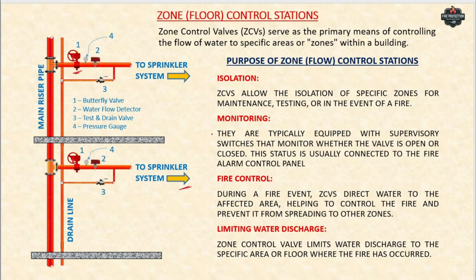And the second is monitoring and alarm integration. These valves are typically equipped with supervisory switches that are connected to the building fire alarm system. If a valve is closed or tampered with, an alarm will be triggered to notify building occupants to escape. Here we have some wires, and these wires are connected to the fire alarm panel. So if someone closes the valve, it will send a signal to the fire alarm panel that the valve is not open. So basically this system is used to monitor the areas.